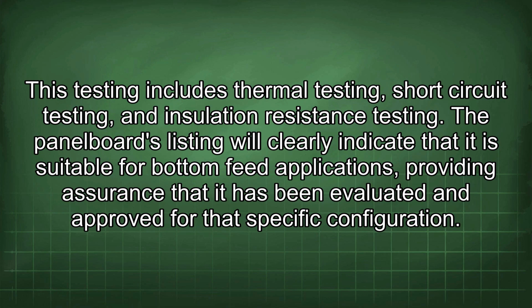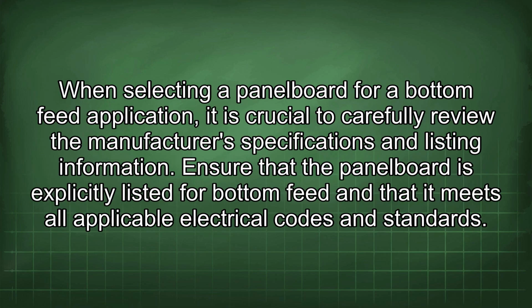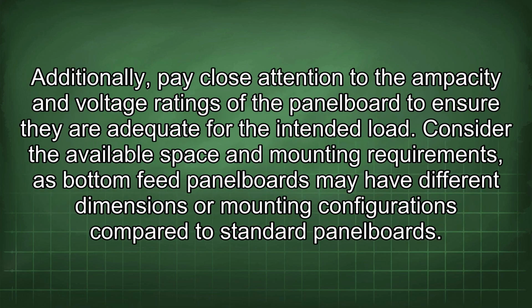The panel board's listing will clearly indicate that it is suitable for bottom feed applications, providing assurance that it has been evaluated and approved for that specific configuration. When selecting a panel board for a bottom feed application, it is crucial to carefully review the manufacturer's specifications and listing information. Ensure that the panel board is explicitly listed for bottom feed and that it meets all applicable electrical codes and standards. Additionally, pay close attention to the ampacity and voltage ratings of the panel board to ensure they are adequate for the intended load.